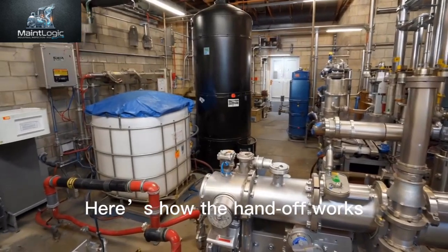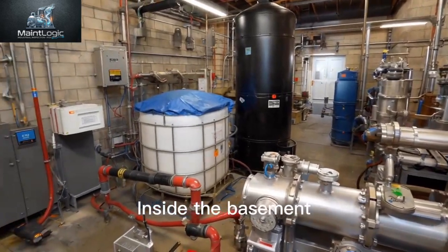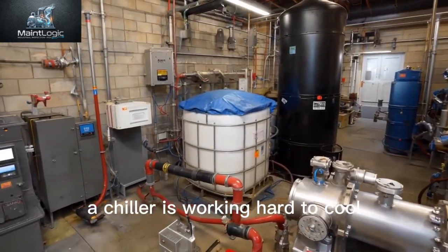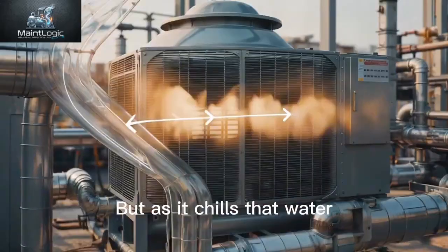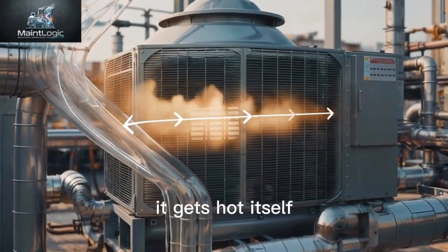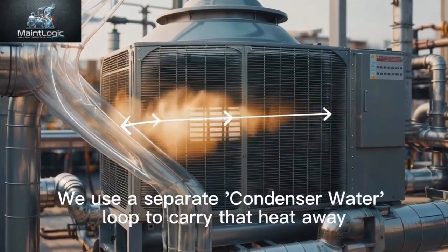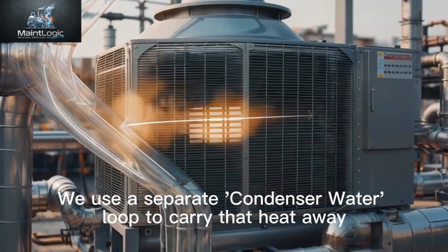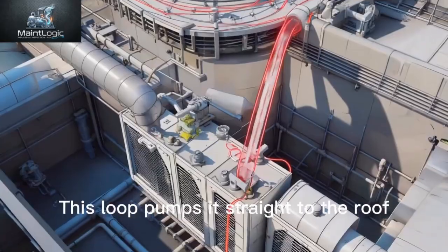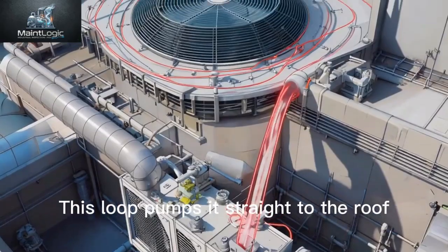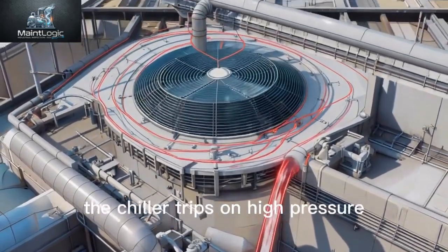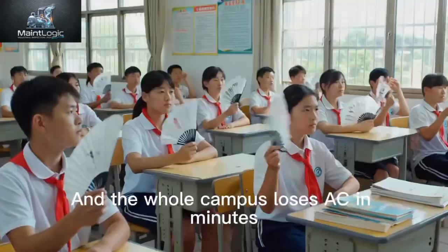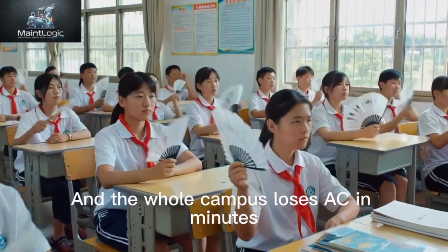Here's how the handoff works. Inside the basement, a chiller is working hard to cool the building's water loop. But as it chills that water, it gets hot itself. We use a separate condenser water loop to carry that heat away. This loop pumps it straight to the roof. If it stops moving, the chiller trips on high pressure, and the whole campus loses AC in minutes.